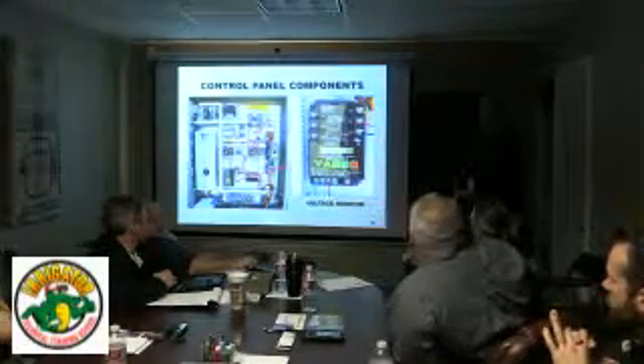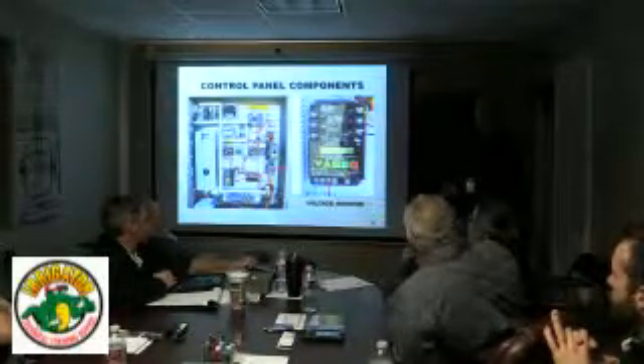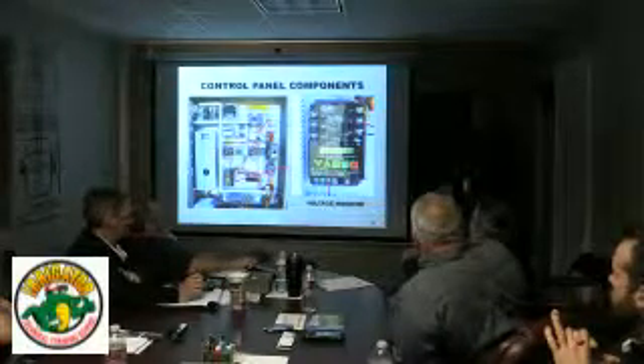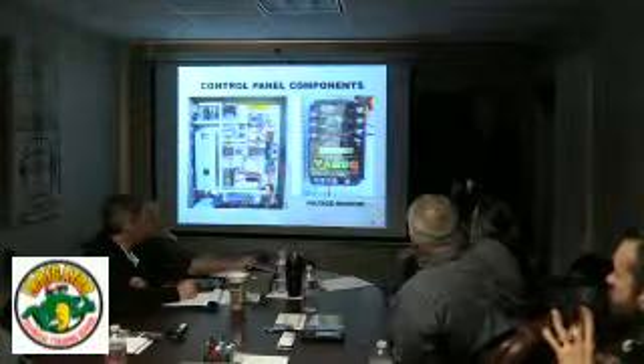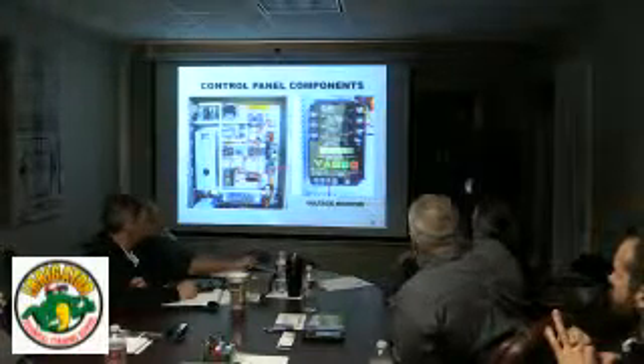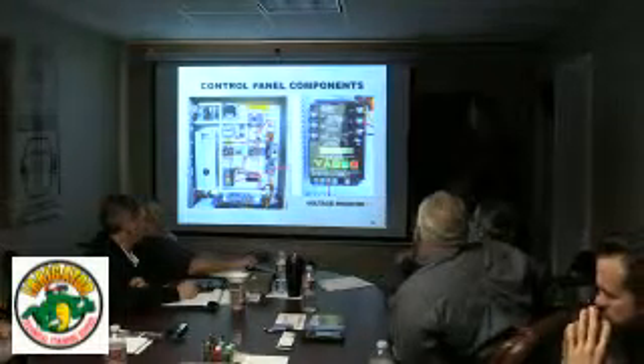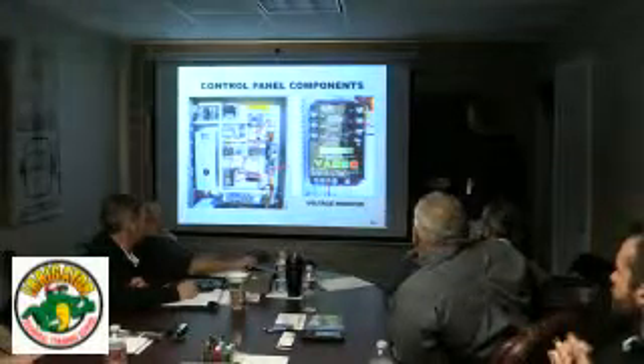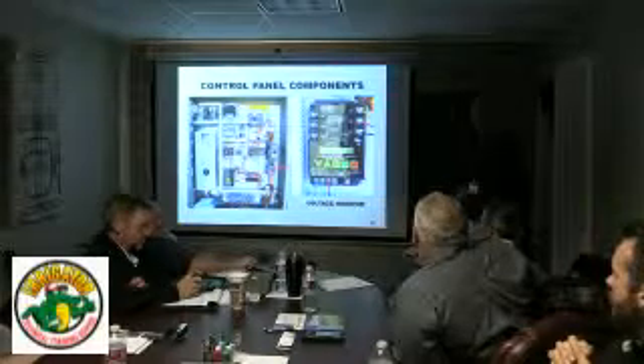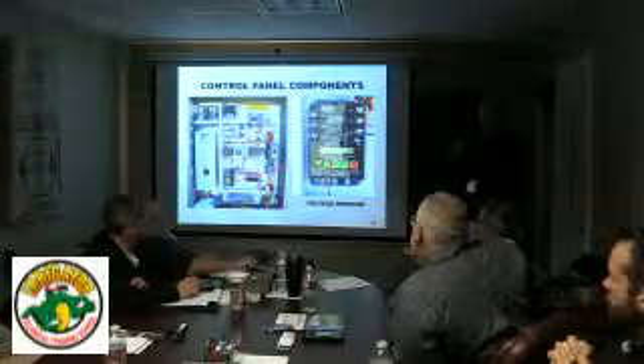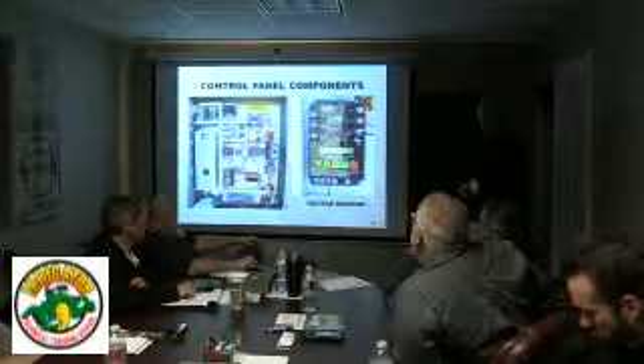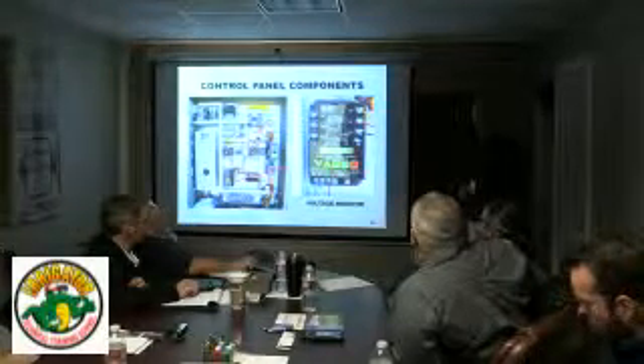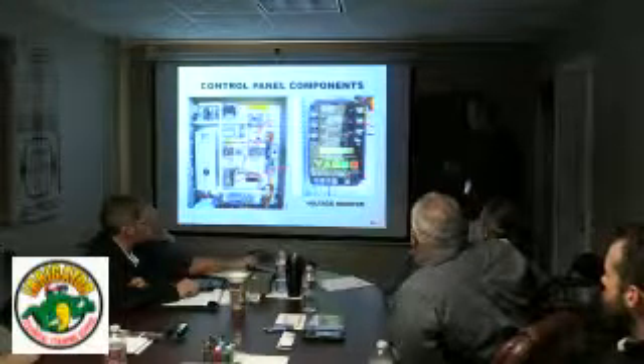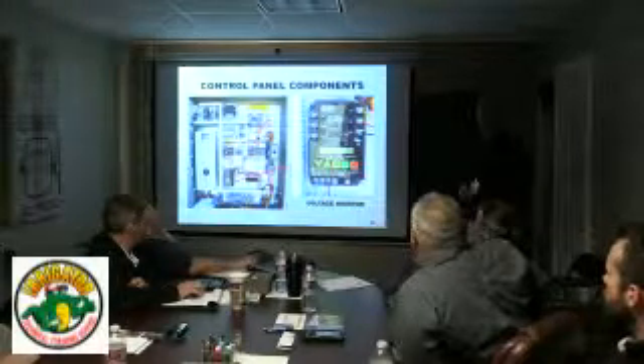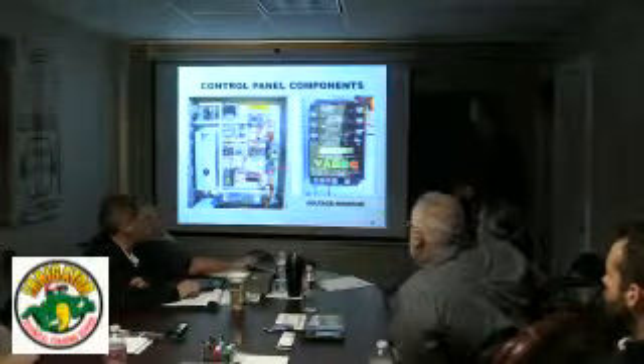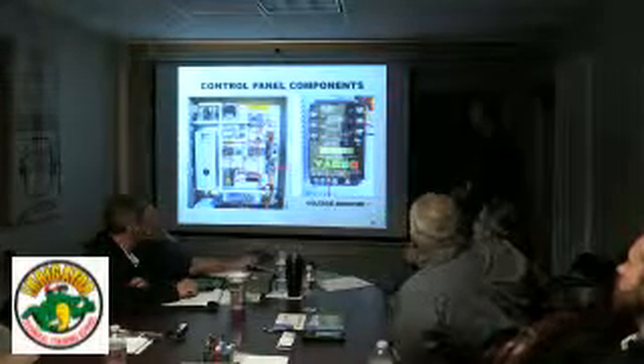Also, the red fault light will be on probably 9 times out of 10. If it sees a power failure or you turn the power off to open the door, it records that. This red light stays on until you reset it. So just because that light's on doesn't mean that there's a fault. You can press the read button and it'll go through. Actually, it might be the fault button. It says it underneath here. I'll have to look at that again tomorrow, but I'm pretty sure it's the fault button. If you press that and keep pressing it, it'll go through a list of the last 12 faults. So it stores faults in there. If you hold that fault button down for about 3 or 4 seconds, it'll clear all the faults. I usually read them and then clear all the faults just because I like the red fault light to go out, and make sure that green load energized is on. That's a voltage monitor.